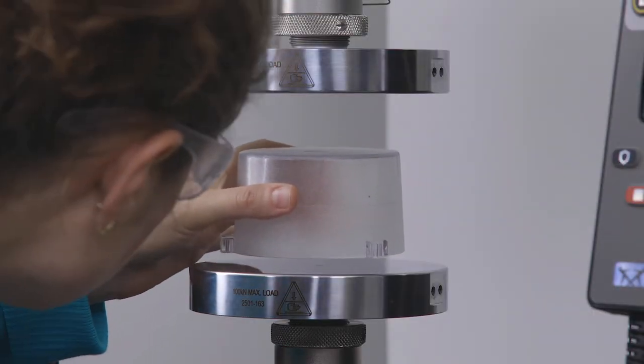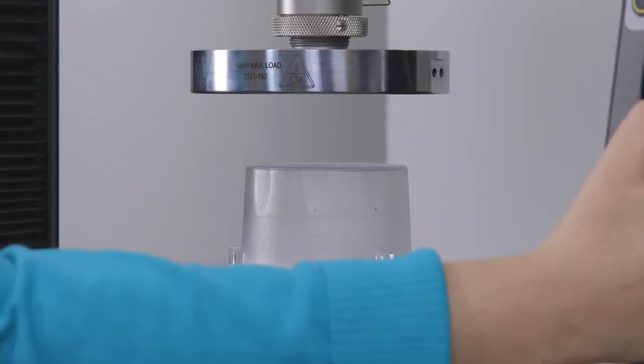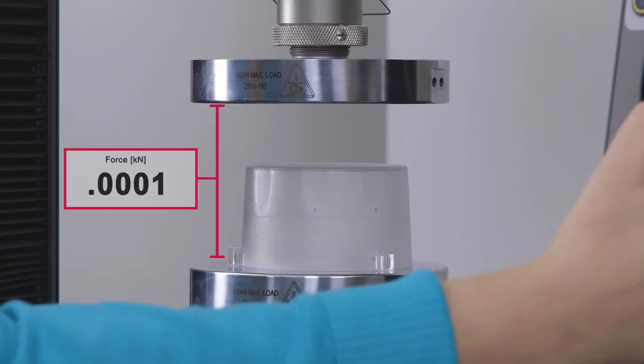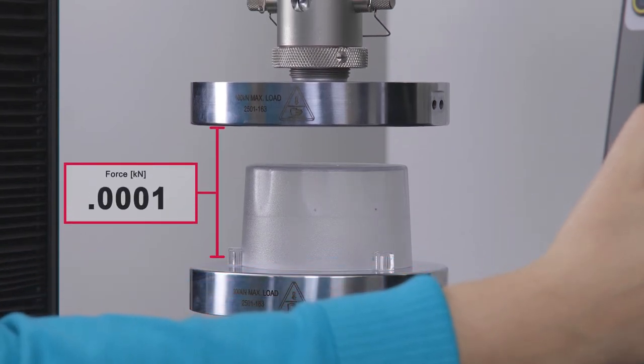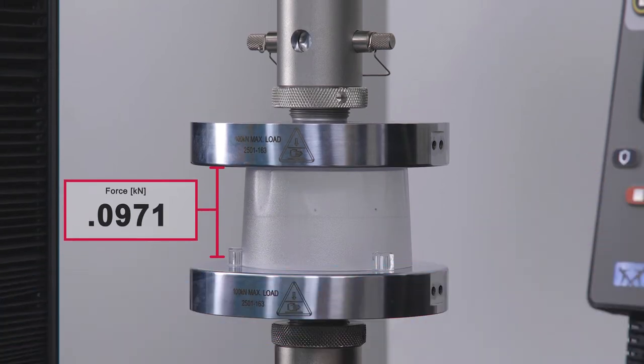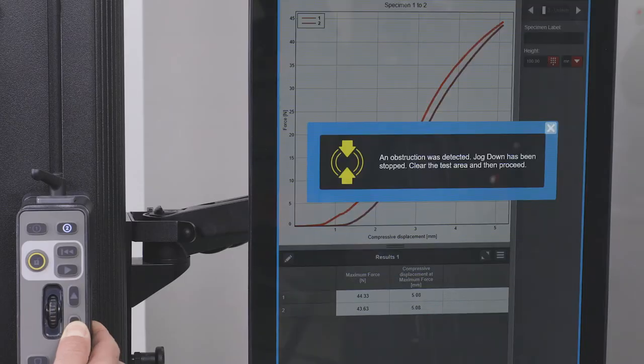Collision Mitigation runs in the background and requires no operator intervention. If the system detects an unexpected increase in force, it will release some of it by reversing the crosshead back to the displacement where the increased force was first detected.